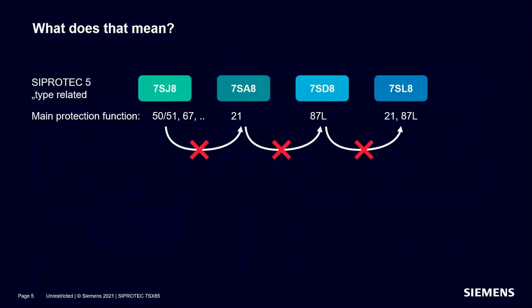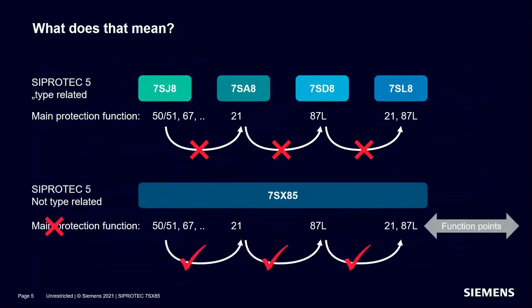As a consequence, the limits between type-related devices disappear, where an overcurrent relay 7SJ8 cannot be changed into a distance relay 7SA8, and a distance relay cannot be transformed into a line differential relay 7SD8. The universal device 7SX85 has no such limits and can be easily modified by the user, who just needs to add the necessary functions to the existing device configuration.